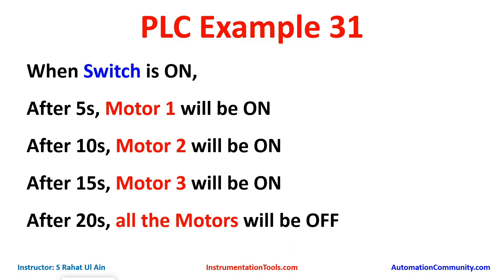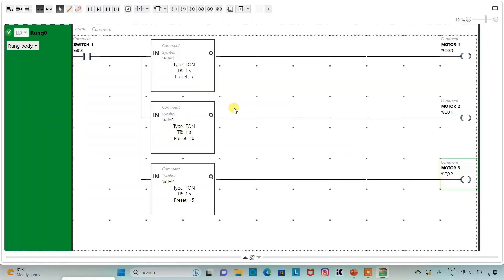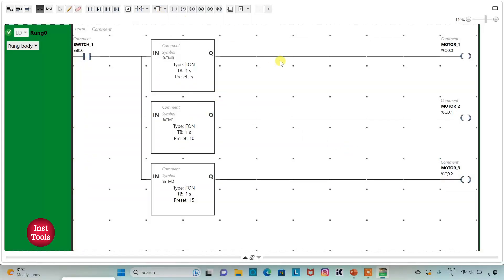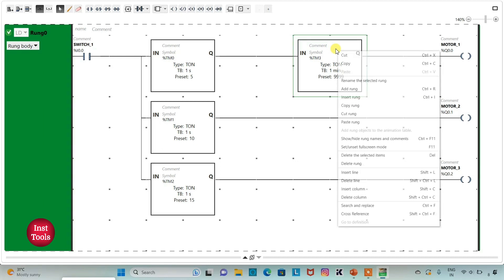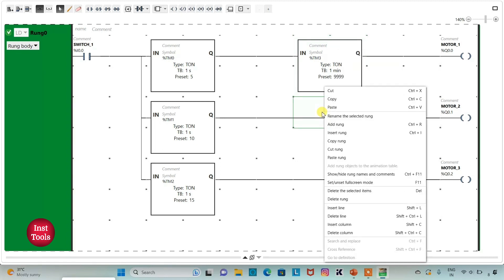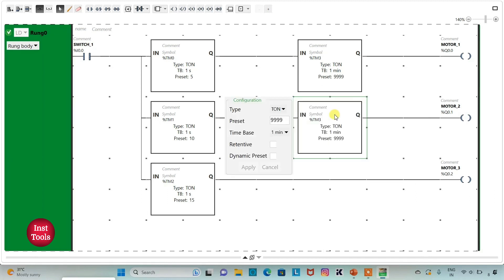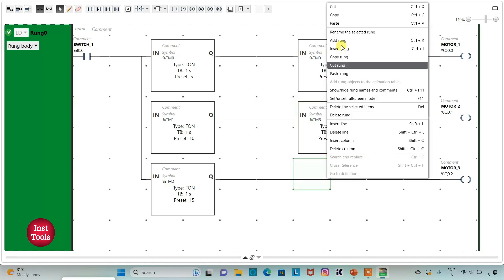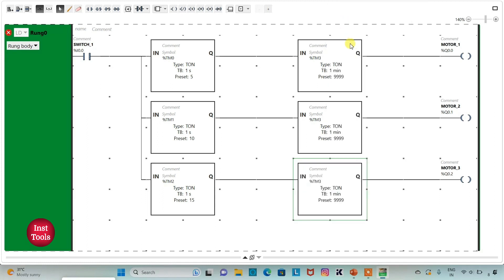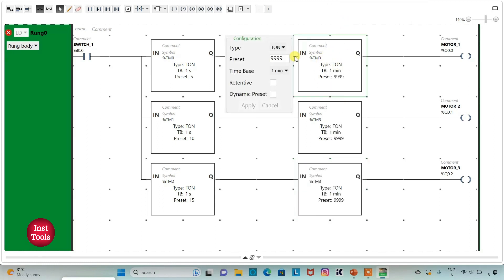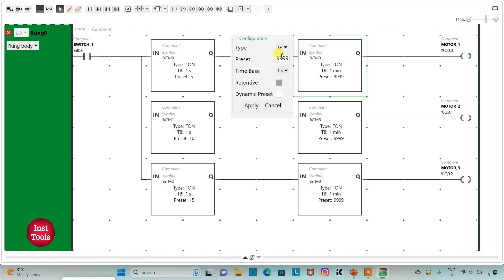Then after 20 seconds all the motors will be off. Here we will use TP for each of the motors. So I will insert another timer here, copy it, and paste it for the other motors. I will change it to TP, set time base to 1 second, and preset as 20. And then apply.